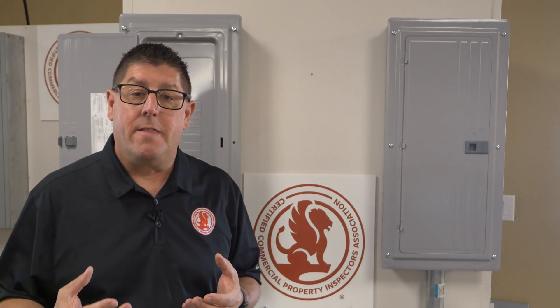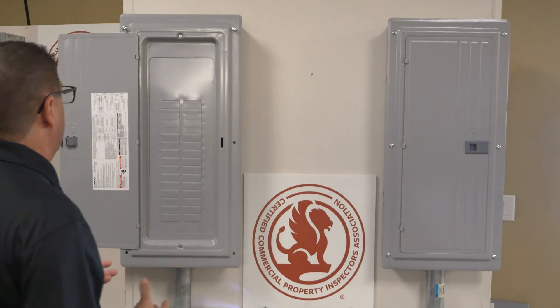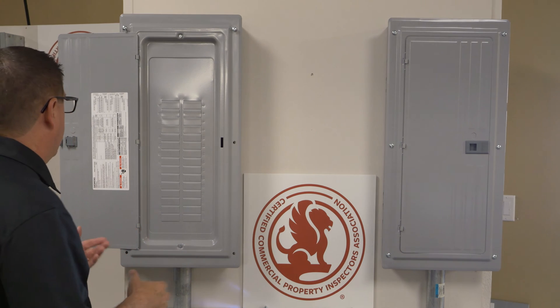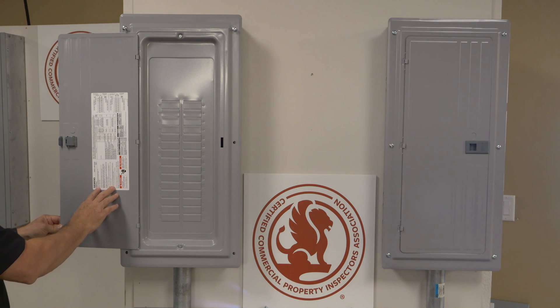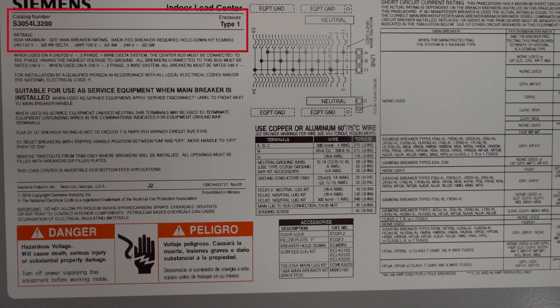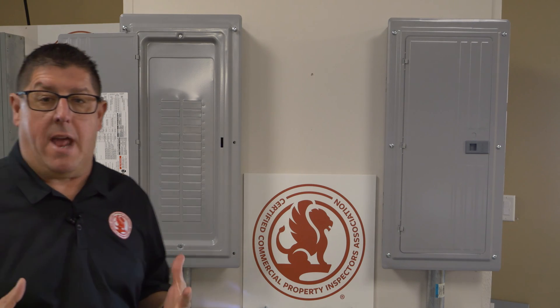In an electric panel, I will have a label plate. That label plate is a factory plate or a generic plate, depending on the type of panel. This is a pretty standard panel, so this is a generic plate. On this plate, I can see the voltage — this is a 200-amp, type 1 panel — and I can see that it's a three-phase, four-wire, 208/120-volt panel.